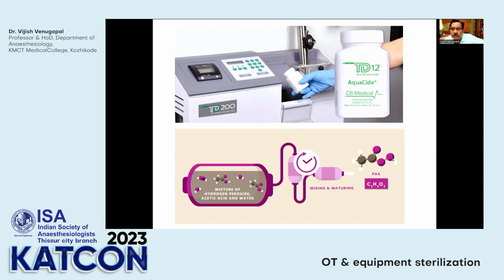Now, peracetic acid decomposes, that is, the end products of the sterilization are not dangerous, and it can either be used in an automated chamber where you add 35% peracetic acid, and automatically it sterilizes the instruments. Now, another way of doing it is by having a mixture of 1% hydrogen peroxide and acetic acid, and then it really gives you peracetic acid, and this mixture you can keep for again 14 days.